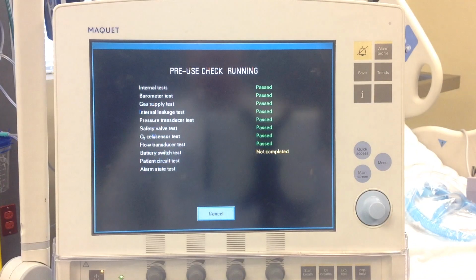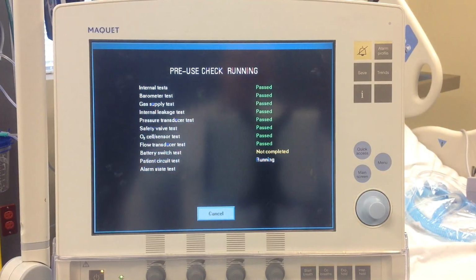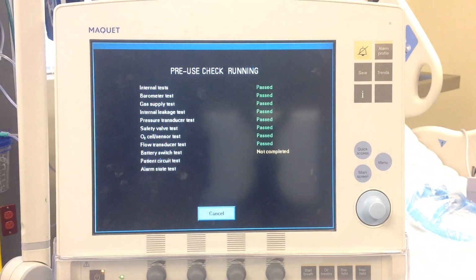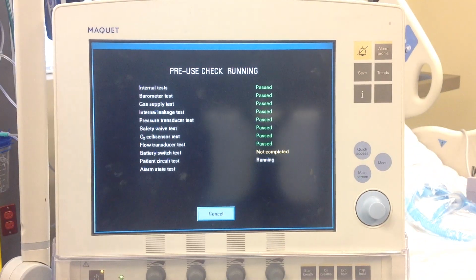Our batteries are not good right now, so a good battery would last about 60 minutes to 70, 80 minutes, something like that. Typically in the hospital you will replace the batteries when the battery life is no more than 45 minutes. At a minimum, the ventilator has 2 batteries on it. They are on the side, and this is what they look like.